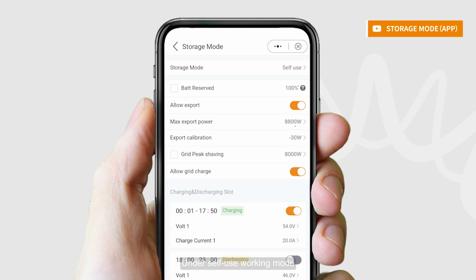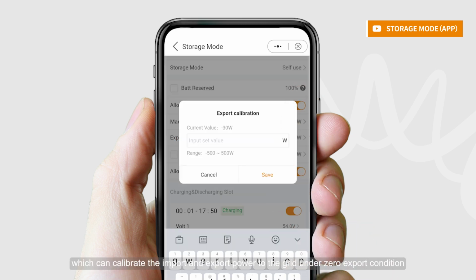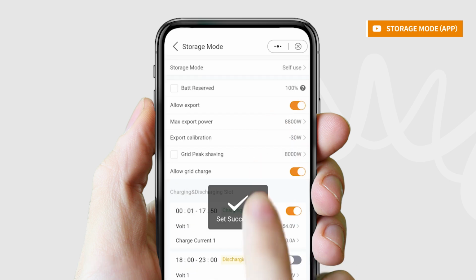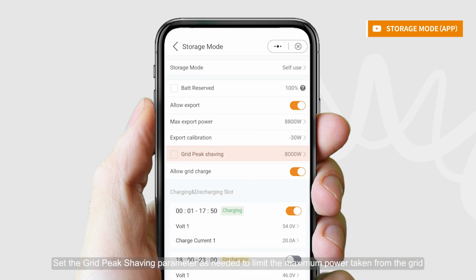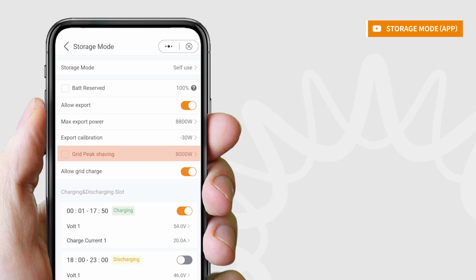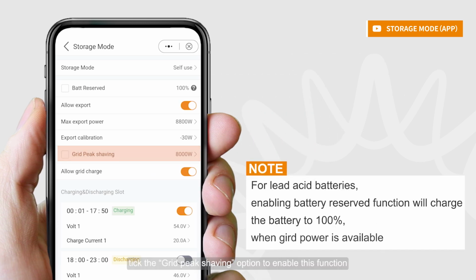Under self-use working mode, turn on the Allow Export option to enable export function. Enter max export power value to limit the maximum power sold to power grid. Set export calibration parameter according to actual applications, which can calibrate the import and export power to the grid under zero export condition. Set the grid peak shaving parameter as needed to limit the maximum power taken from the grid. Tick the grid peak shaving option to enable this function.